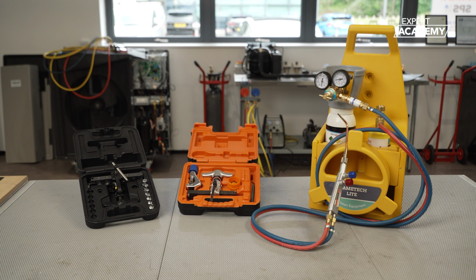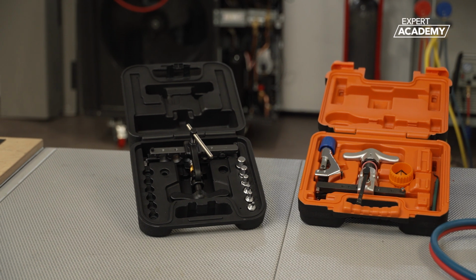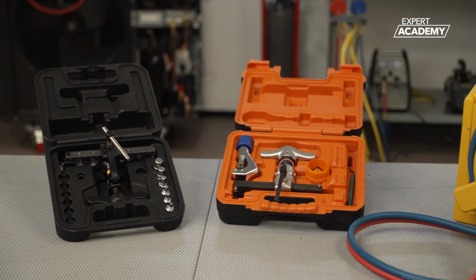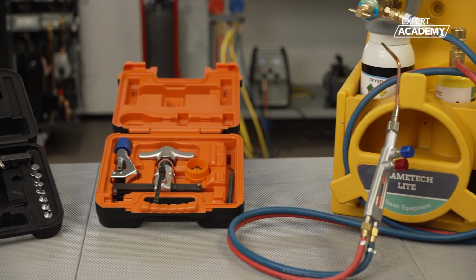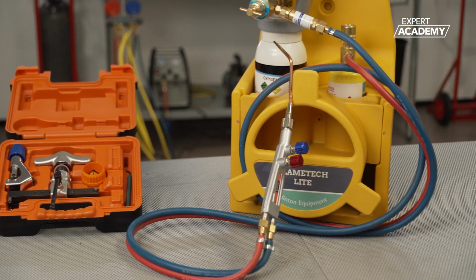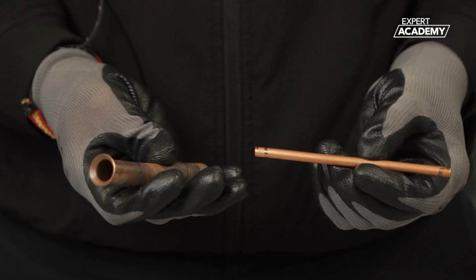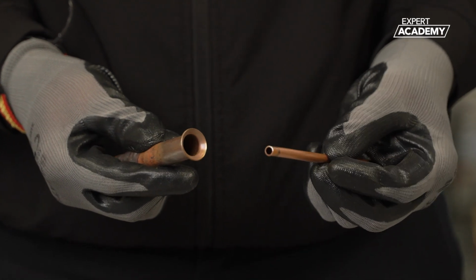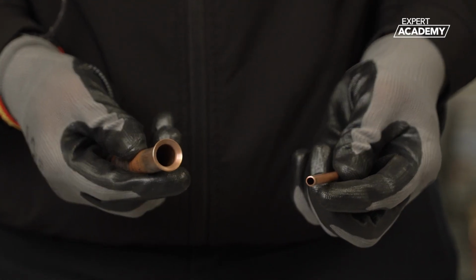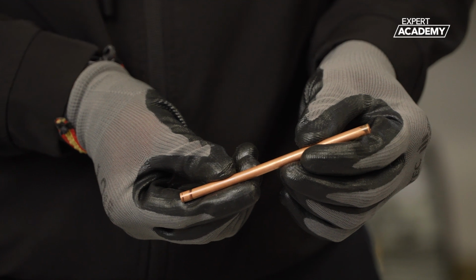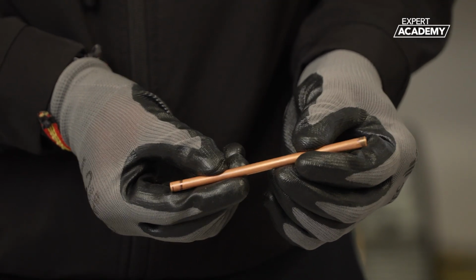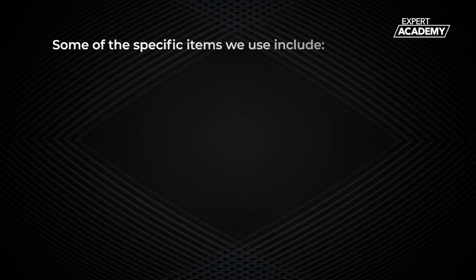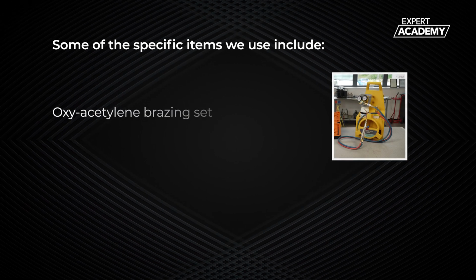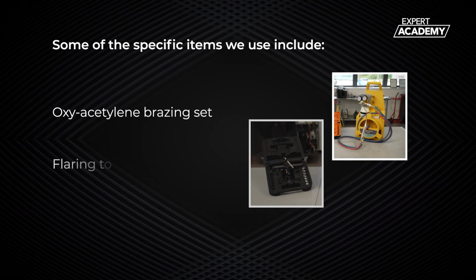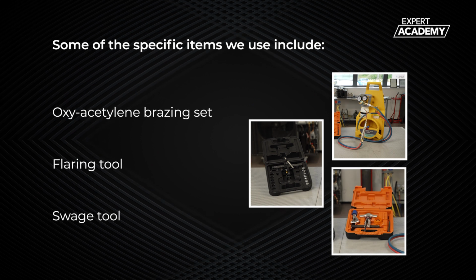Some of the tools mentioned earlier may be necessary for maintaining heat pumps and replacing components. However, when installing refrigerant lines in split heat pumps or air conditioning systems, these next tools are more commonly used. The copper pipe used for refrigerant lines features a thick wall design with a high pressure rating, different from the types commonly used in plumbing applications. Consequently, the jointing techniques required are different. Some of the specific items we use include an oxyacetylene brazing set, a flaring tool, and a swage tool.